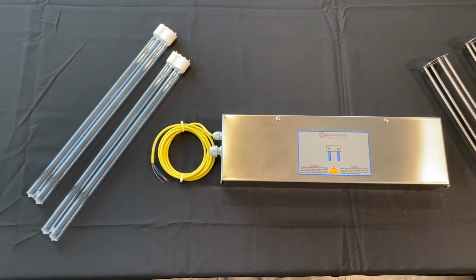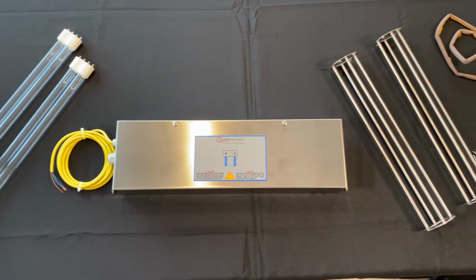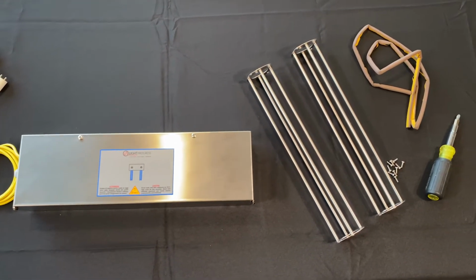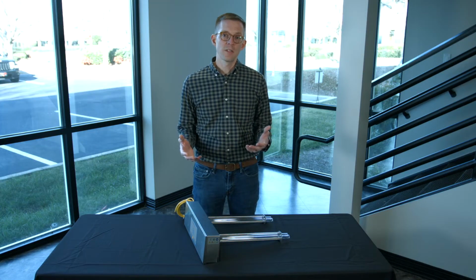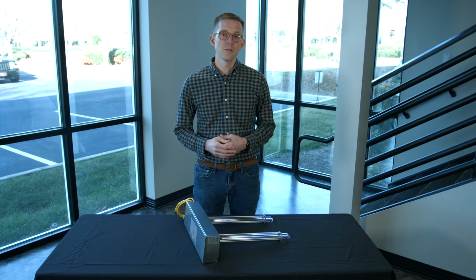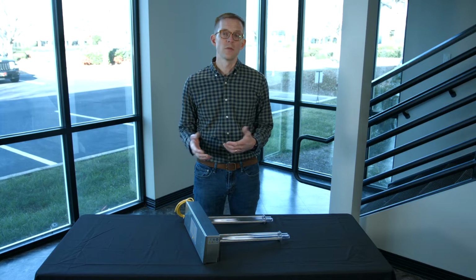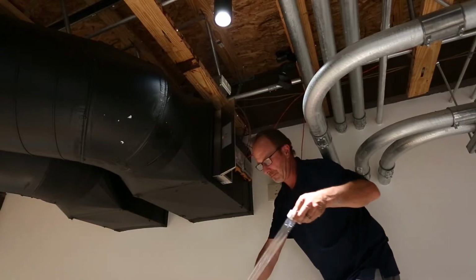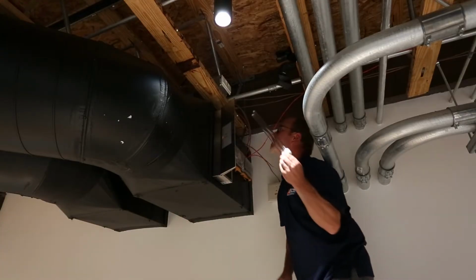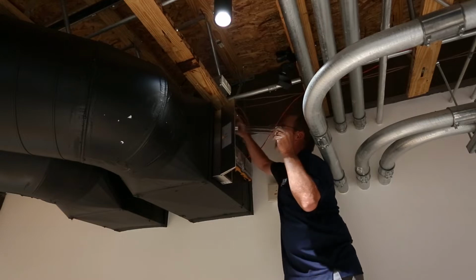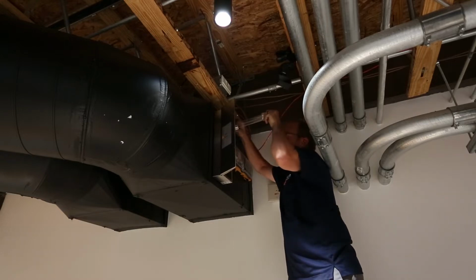This fixture includes 2 UVC lamps for a pretty high dose of UVC energy, and depending on the specifications of your HVAC system, including the CFM rating for your ductwork, you may actually need to install a couple of these units together depending on the level of dose that you're looking for your HVAC application.